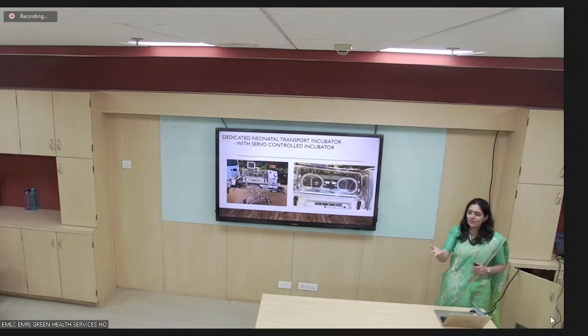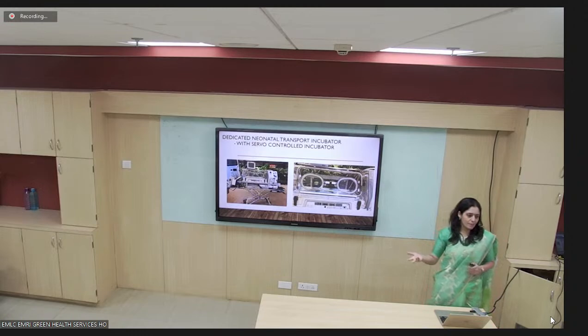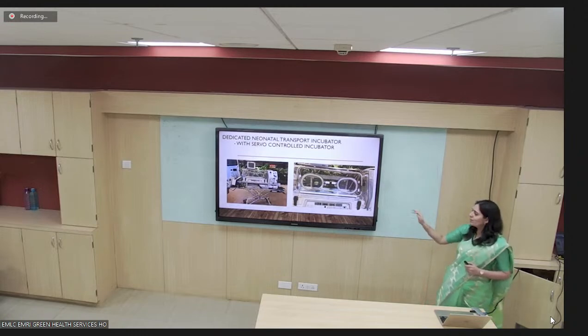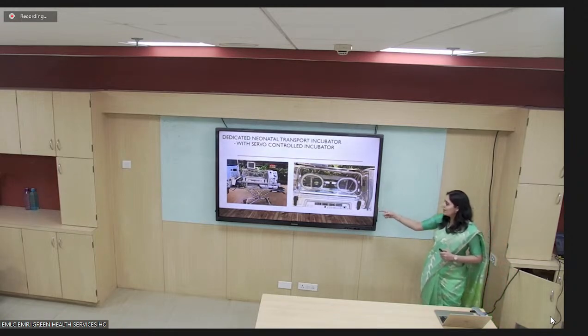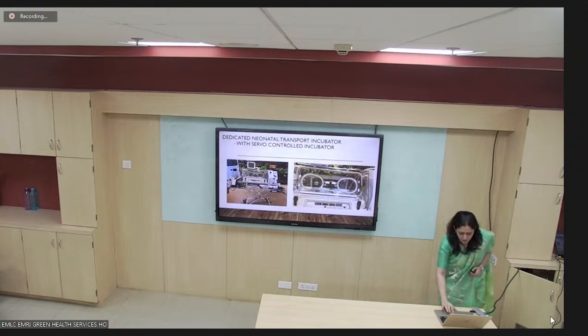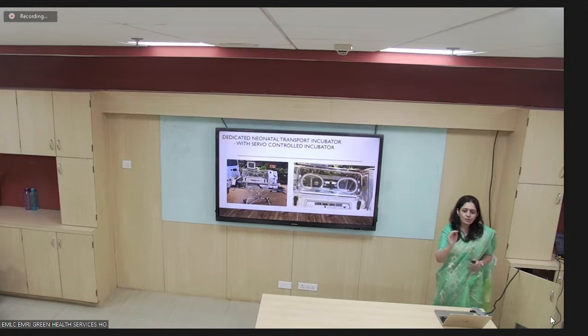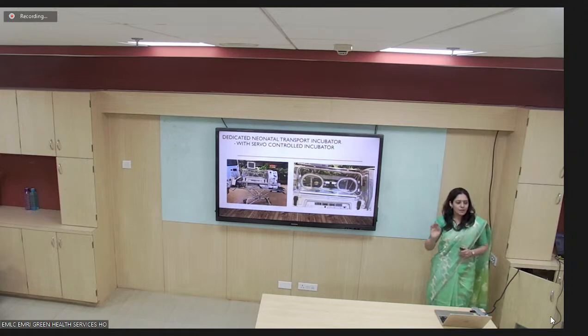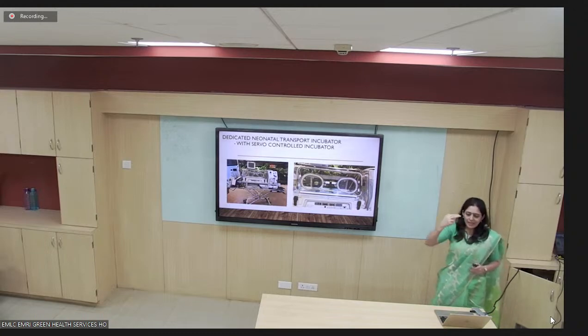You might receive the baby at 36 degrees, for example, or 35 degrees. If you put this baby into the incubator, this is the place where you adjust the temperature. These are the norms, and we reach a temperature of 36.5 to 37.5, which is normal. So this is servo control. Automatically the heat will be generated and circulated around the baby.